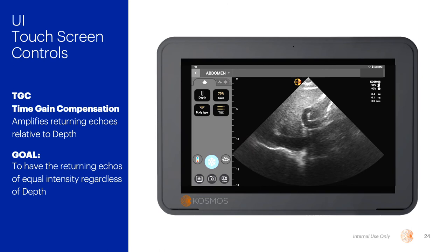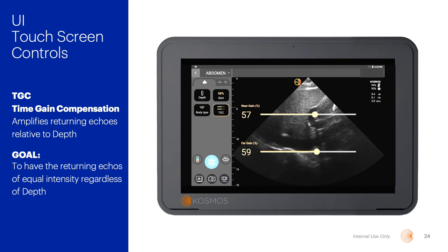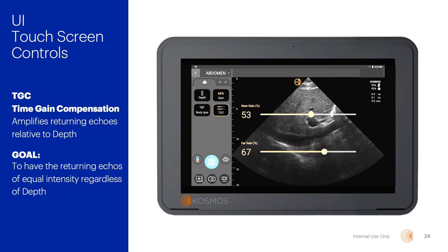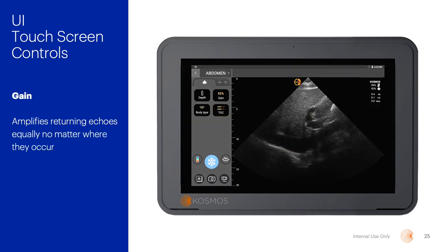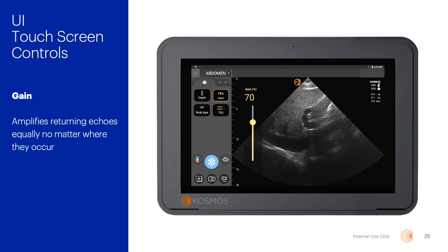The next two controls also assist with compensating for the attenuation of the signal. Remember, these are receiver controls and do not control the output signal of the transducer. The first is called TGC, or time gain compensation. It compensates for the additional time the signal took to travel to and from deeper structures as compared to those with a shorter round trip travel distance. In essence, the control amplifies returning echoes relative to depth, with the goal of displaying returning echoes of equal intensity regardless of depth. The next control is called gain, which acts similar to a volume control — it amplifies returning echoes equally no matter where they occur. One common error is to begin with the gain too high and then use the TGC to suppress the signals; it is important to remember these controls work in conjunction with one another.